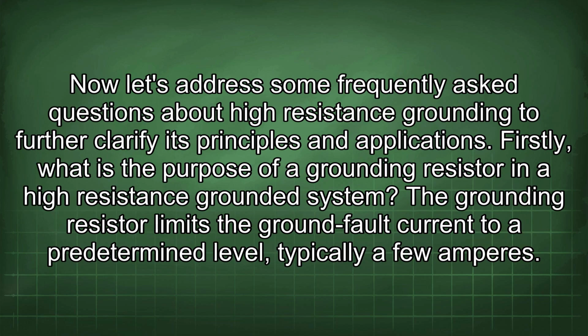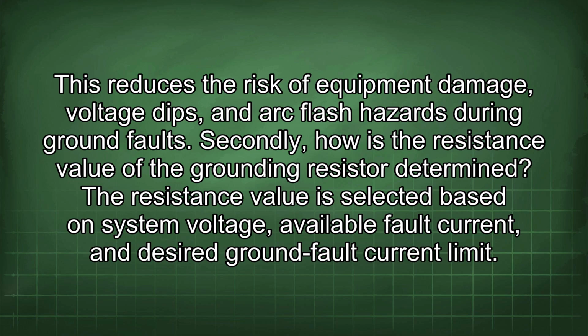Now let's address some frequently asked questions about high-resistance grounding to further clarify its principles and applications. Firstly, what is the purpose of a grounding resistor in a high-resistance grounded system? The grounding resistor limits the ground fault current to a predetermined level, typically a few amperes. This reduces the risk of equipment damage, voltage dips, and arc flash hazards during ground faults.